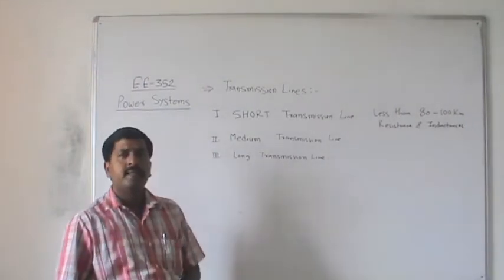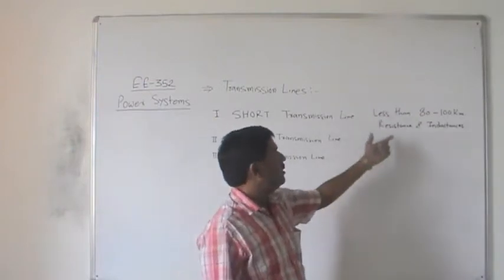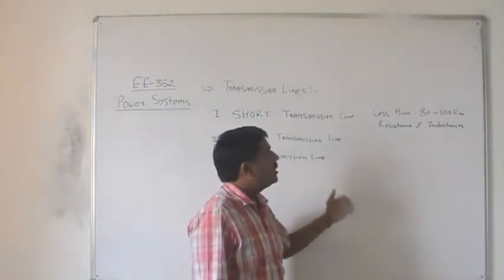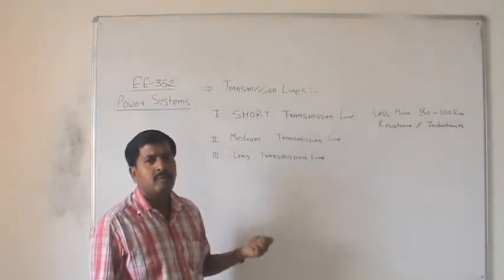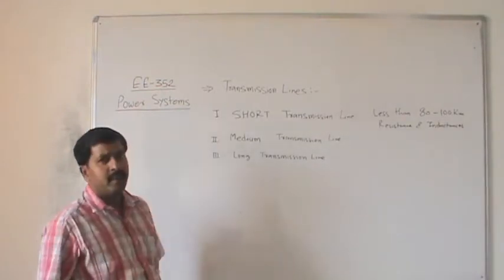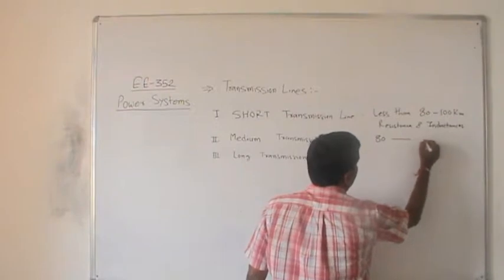We neglect capacitance in the short transmission line. When analyzing a short transmission line, we only consider resistance and inductance. The length is so small that the capacitive effect is negligible. For medium transmission lines, the length is between 80 km and 150 to 200 km.